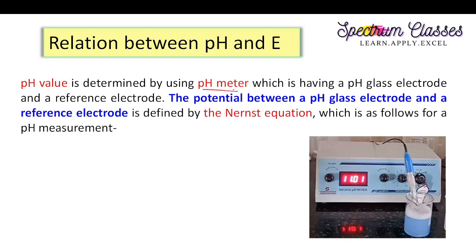The pH meter is used to determine pH values. It comprises two electrodes to make the assembly complete: one is the pH glass electrode and the other is the reference electrode. The potential difference between the pH glass electrode and the reference electrode is measured using the Nernst equation, and from there we can determine the value of pH.